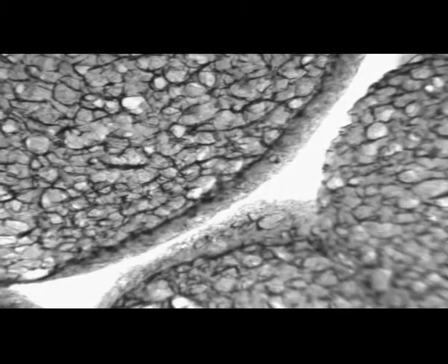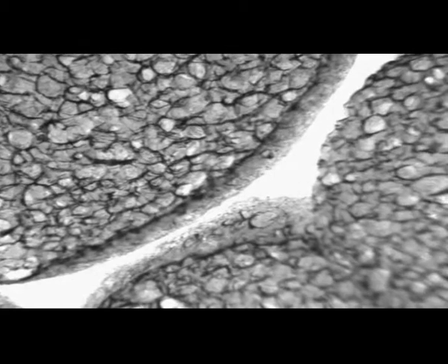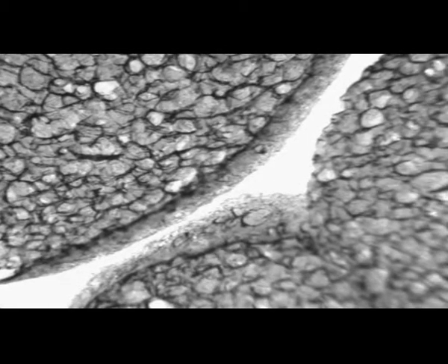With the EPS cell structure, the bead molding process leaves voids between beads where water can enter. Although the individual beads of EPS are closed cell, the voids between the beads can absorb significant amounts of water, which reduces the already lower in-service R-value of EPS compared to XPS.